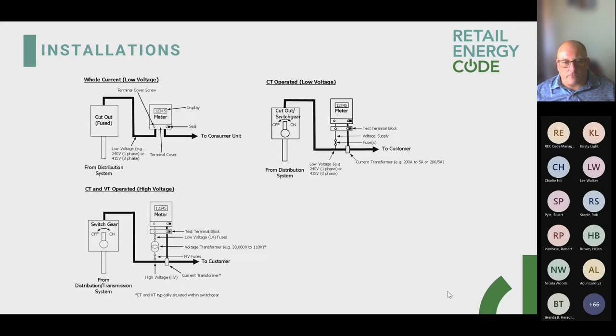We'll take whole current first of all. Whole current metering is what we would class as our low voltage type activities - small shops, very small commercial and domestic, main domestic premises. There are some domestic premises that fall outside this, and I'm not going to differentiate between three phase and single phase at the moment - I'll mention that in a little bit. But in effect, the distribution network operator is responsible from the local distribution zone takeoff point right up to this little fuse that's now in your customer's property. From that point onwards, it then becomes the meter operator's responsibility.